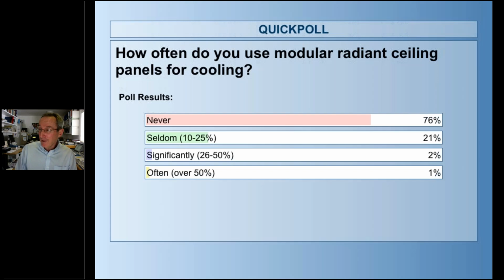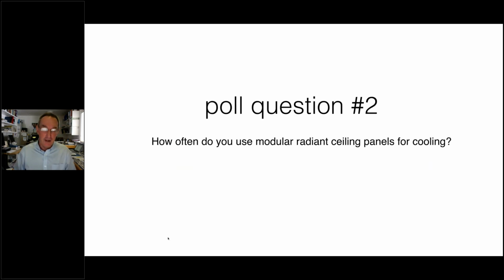Well, again, we're talking about it in hydronics because of the overall trends towards building electrification, cooling, and an increased number of buildings that need cooling. When you're looking at this from the standpoint of reducing energy use, there are significant advantages. In Hydronics 28, we go into this in more detail, but to summarize, in average conditions, for example in upstate New York, we would say about 70% of the total cooling load is sensible cooling. The other 30% is latent cooling, moisture removal.